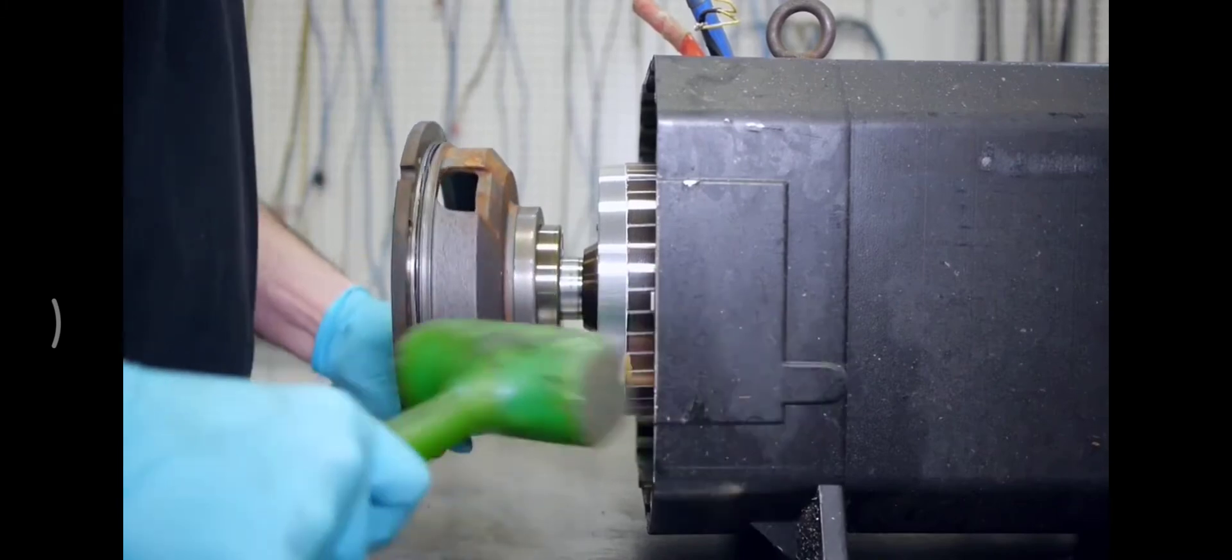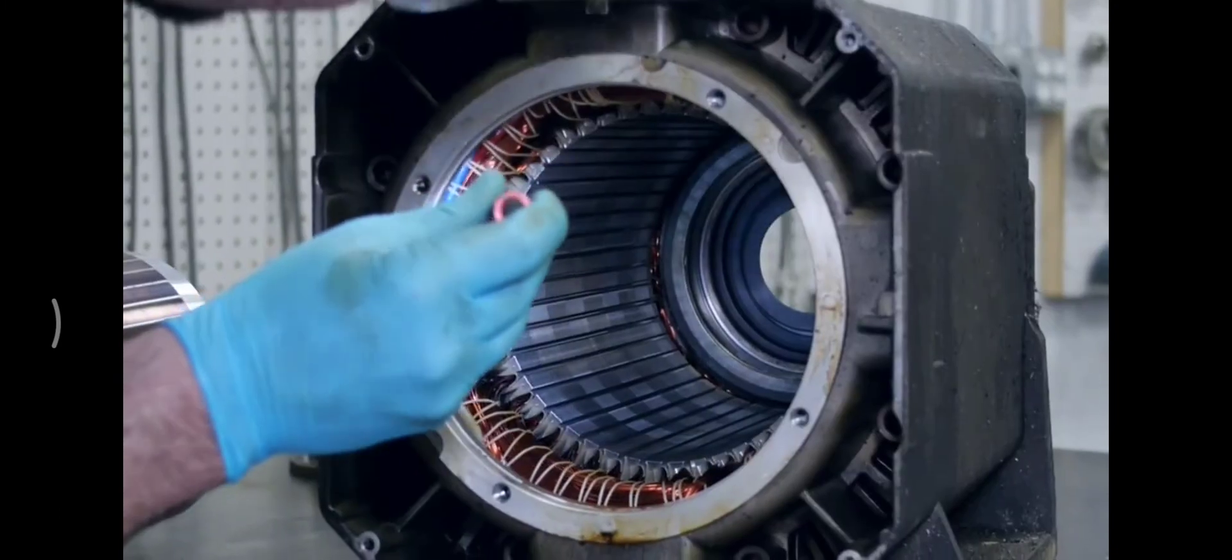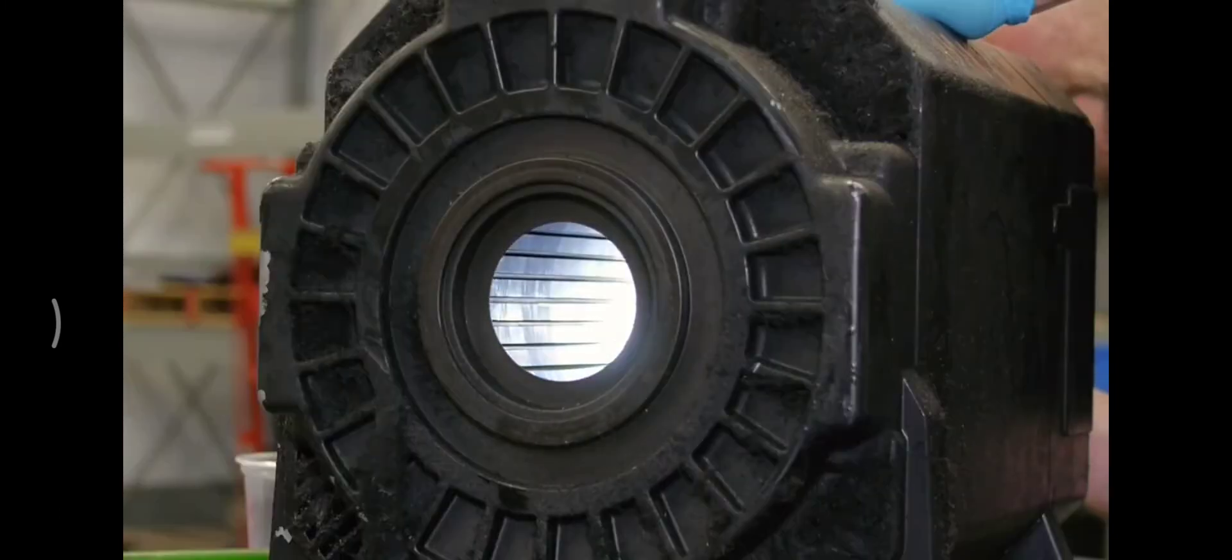The rotor is removed from the stator and the bad bearings removed. Our technician visually inspects the motor windings and the bore of the stator for obvious trouble spots.